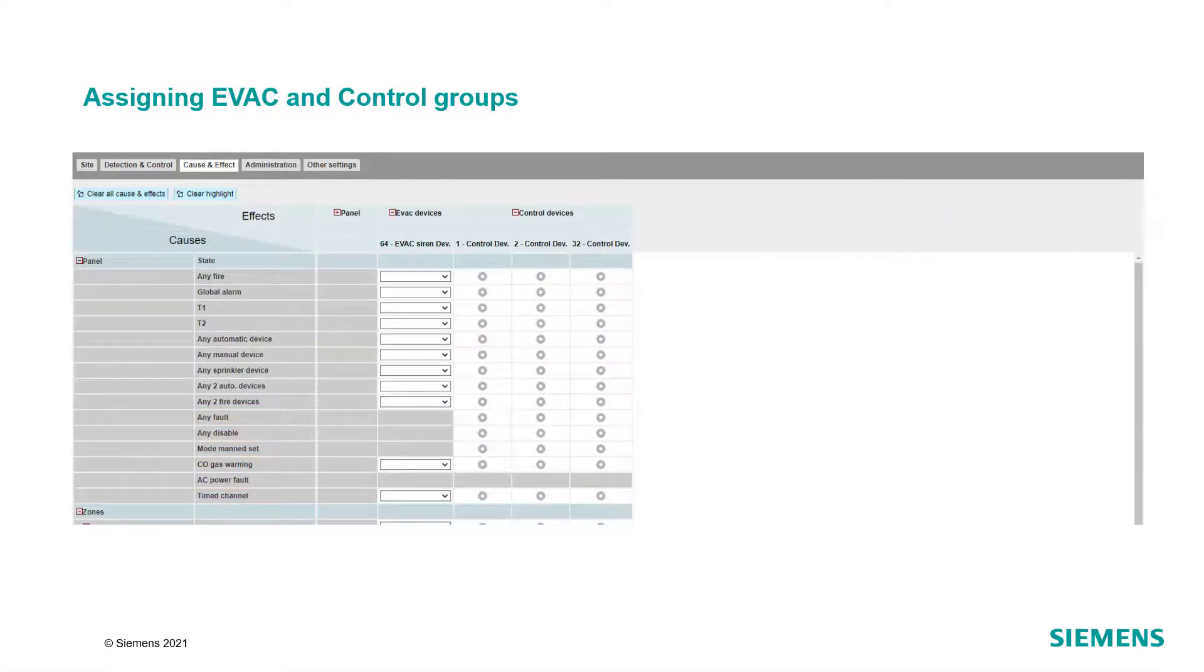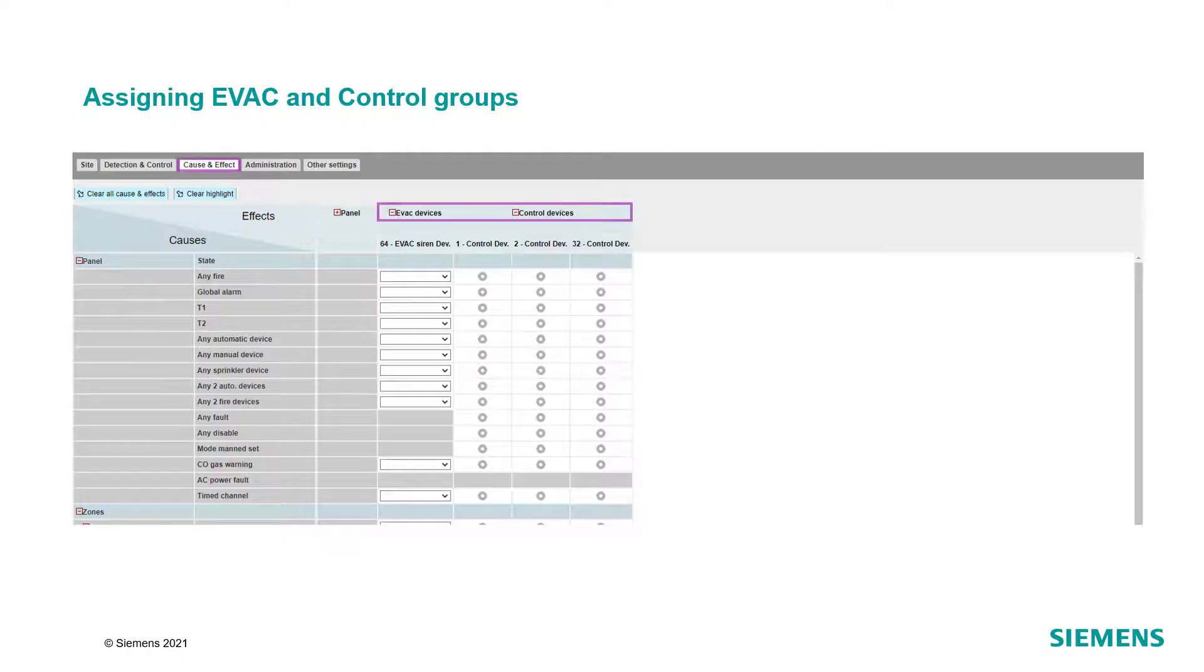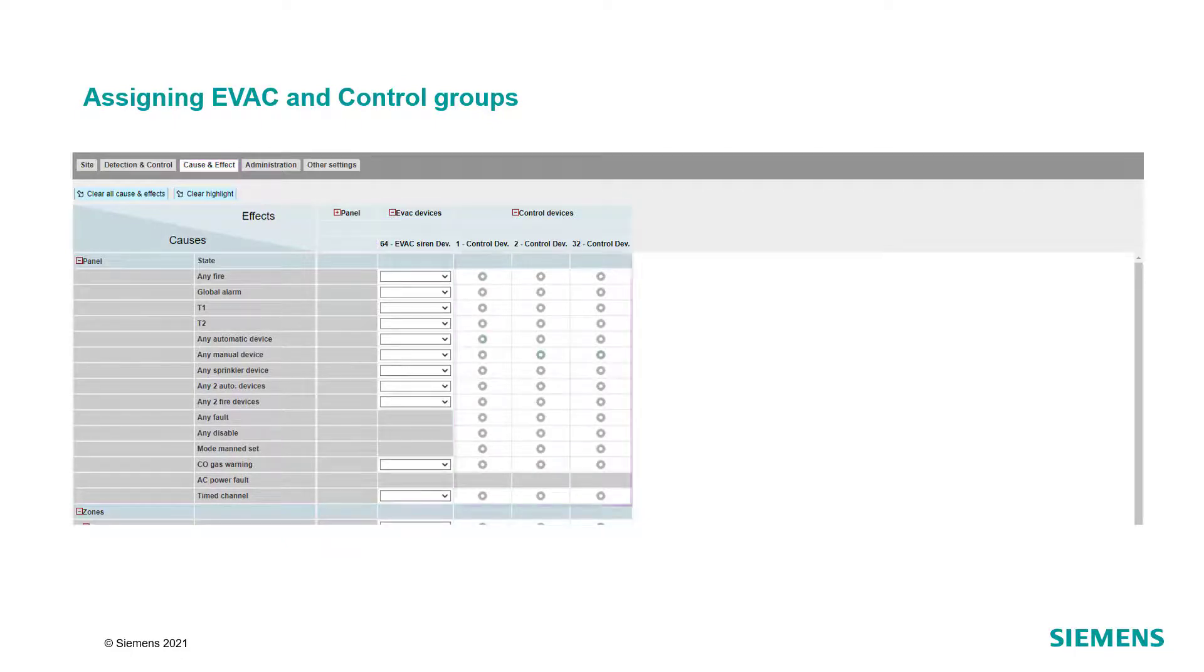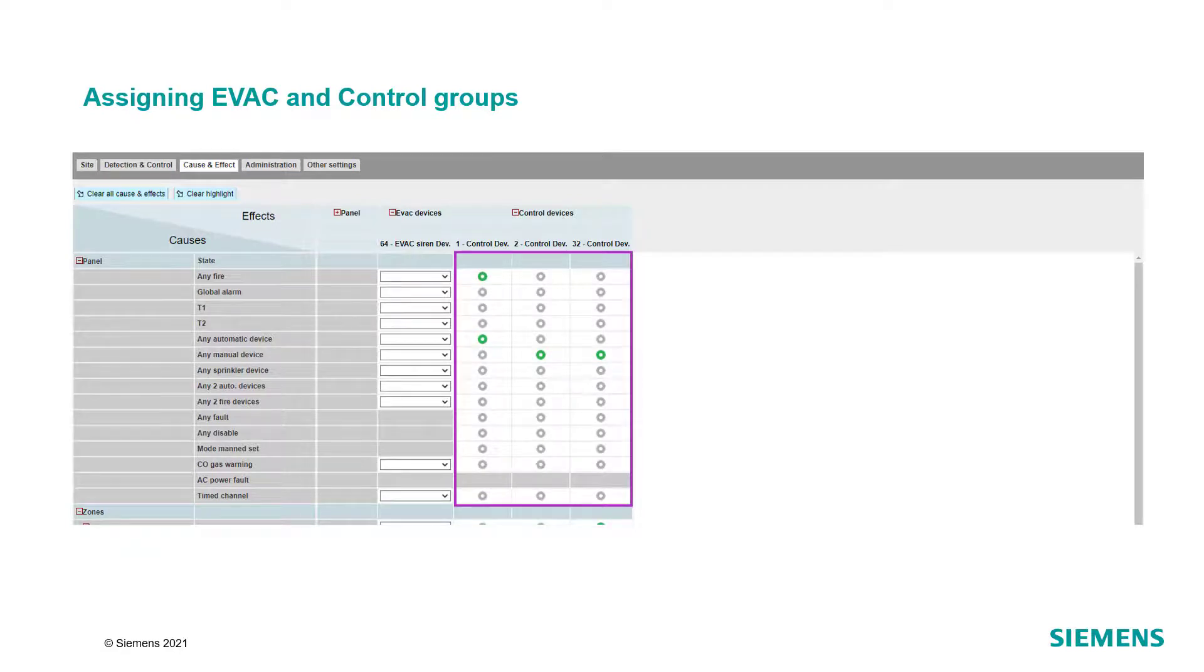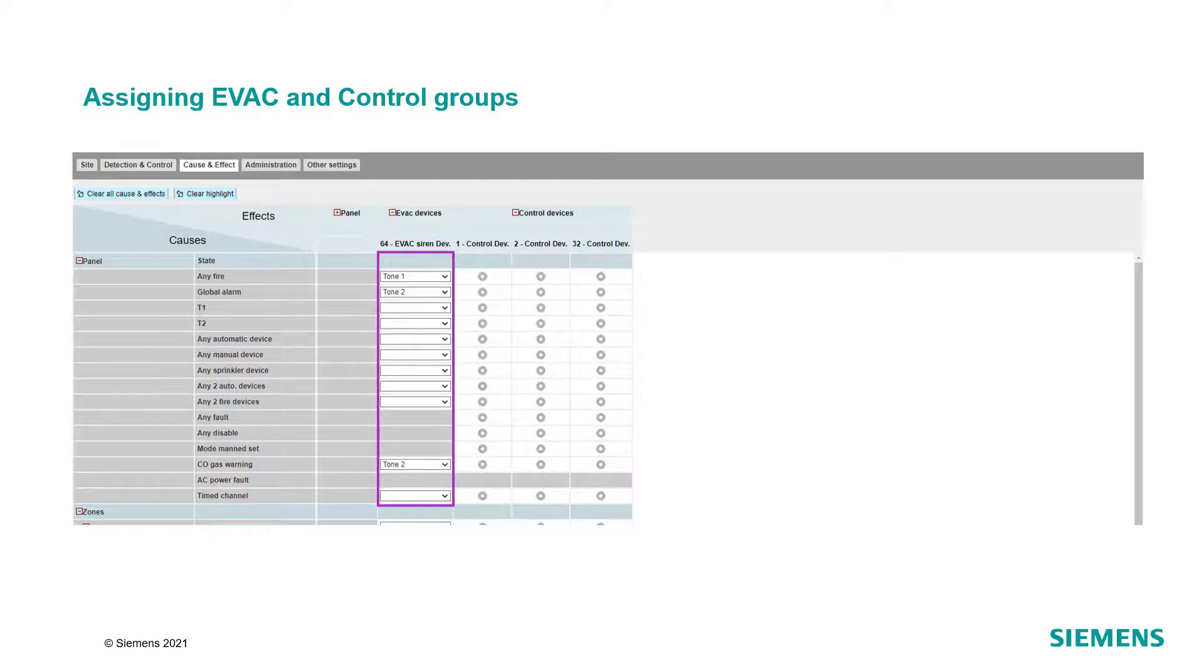Now, go to the Cause and Effect tab and expand the evac and control devices. Activate each event from the panel that should activate the different control groups. For evac groups, a tone can be defined to be played in case an event is activated in the panel.